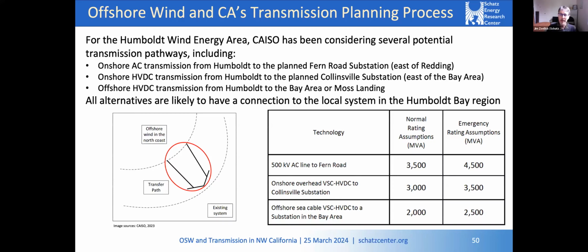I'll point out the table in the lower right-hand corner, showing the capacities for these different types of lines. A 500 kV AC line, in this case going to Fern Road, has a normal rating of 3,500 MVA. MVA is essentially equivalent to megawatts—volts times amps is watts, so MVA is essentially megawatts. So 3,500 MVA would be 3,500 megawatts, and then there's an emergency rating.